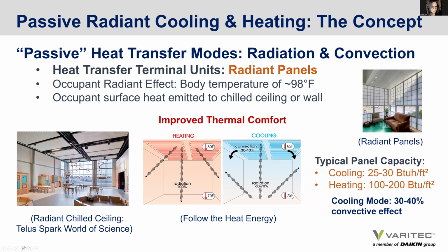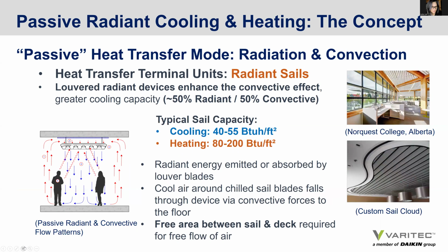There are radiant sails, which are more effective in cooling because of the convective effect. These are louvered devices in the ceiling that allow air above the radiant sail to be cooled and through convection pass through the actual radiant sail, adding more heat transfer capacity in cooling mode of around 40 to 55 BTUs versus 20 to 30 with a radiant panel.